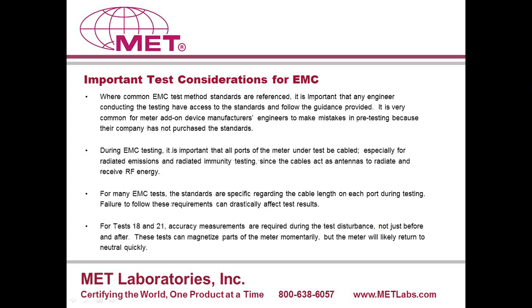Now, just to wrap up some of the important test considerations for EMC. Most times, a meter add-on device manufacturer will perform some quick pre-testing in-house before submitting the samples to a test lab for official testing. They may or may not have access to these international standards like the 61000-4- standards, which call out the specific test methods and test procedures. So it is possible that the way you perform this pre-testing, you may get different results based on how you conducted the testing versus the testing that actually takes place in the lab. So it is important to make sure that you have access to all the right standards and follow all the guidance that is provided therein.